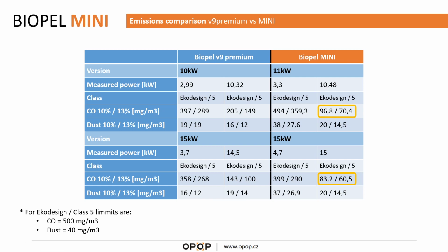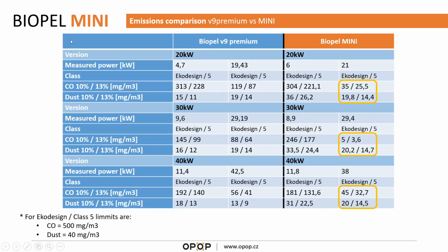The higher the power we have, the better emissions we get. So if you check here the comparison between 20, 30 and 40 kilowatts, you see that, for example, the 40 kilowatt boiler has carbon of only 45 milligrams, and the 30 kilowatt version has carbon emissions of only 5 milligrams. Before it was 88. So you see that the emissions are better, and we will work in the future to reduce the emissions even lower. As you can see here, in the left bottom corner, for the eco design standard and class 5 limit, the carbon is 500 milligrams and dust particles are 40 milligrams.